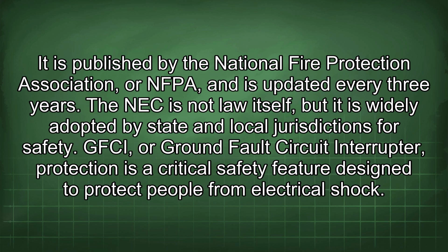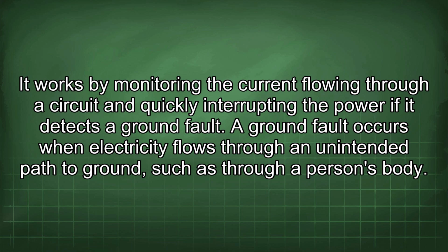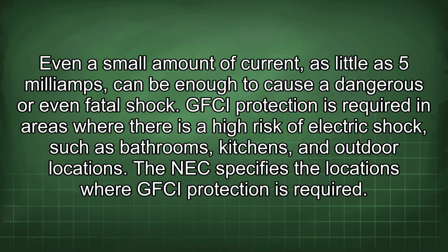GFCI, or Ground Fault Circuit Interrupter protection, is a critical safety feature designed to protect people from electrical shock. It works by monitoring the current flowing through a circuit and quickly interrupting the power if it detects a ground fault. A ground fault occurs when electricity flows through an unintended path to ground, such as through a person's body. Even a small amount of current, as little as 5 mA, can be enough to cause a dangerous or even fatal shock. GFCI protection is required in areas where there is a high risk of electric shock, such as bathrooms, kitchens, and outdoor locations. The NEC specifies the locations where GFCI protection is required.